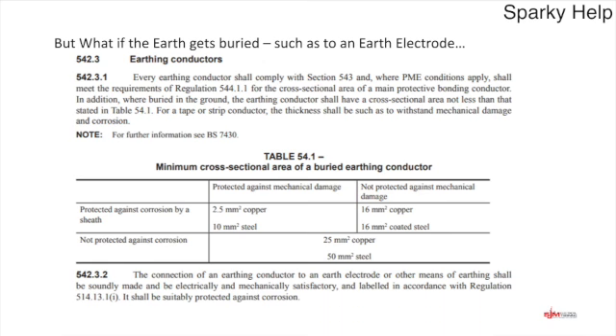So we have a set of regulations that says if you bury earthing conductors, and it is not protected against mechanical damage but it is protected against corrosion, in other words it's got a green and yellow sleeving around the outside, a sheath on it, then you can get away with a 16mm copper. So the moment you bury it, then it has to be 16mm. However, if you look across, if it is protected against corrosion and you put it in conduit and trunking or something, the minimum in theory you could get away with is a 2.5mm squared copper cable. Okay, but obviously you would check to make sure it is correct, but these are the minimum cross-sectional areas.